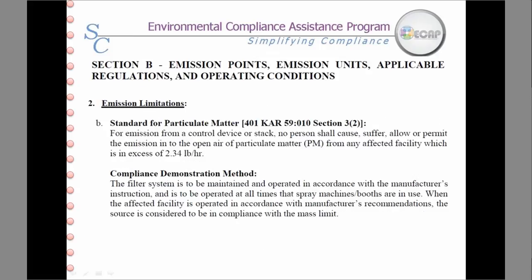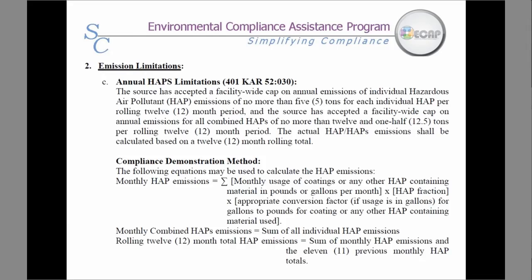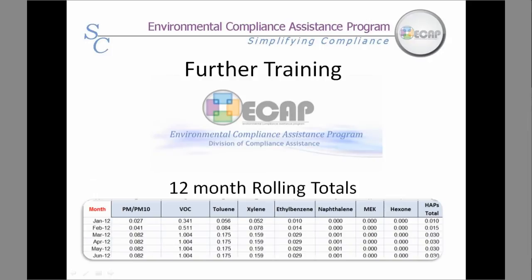Another common emission limit is for particulate matter. In this case, the filter system is to be in place in order to be in compliance with the emission limit. Hazardous air pollutant and VOC limitations usually require a 12-month rolling total to be kept, and your permit explains how to calculate the rolling total — usually in Section D. If you are unsure how to perform the required 12-month rolling total emission calculations, please contact the Division of Compliance Assistance for assistance or training. DCA can assist small businesses with creating easy, user-friendly rolling total spreadsheets.